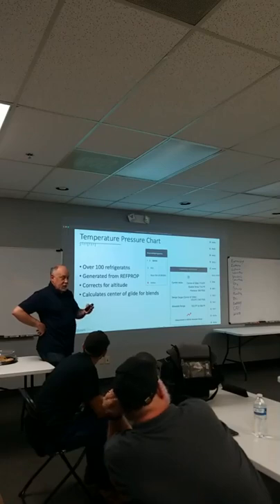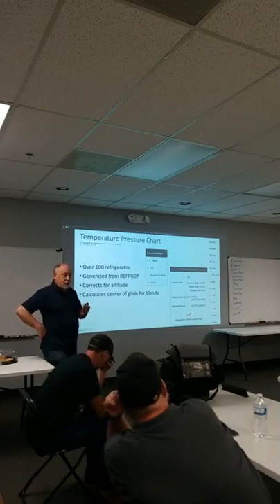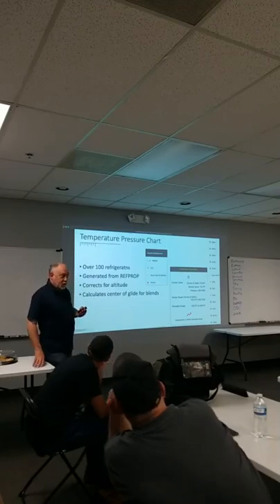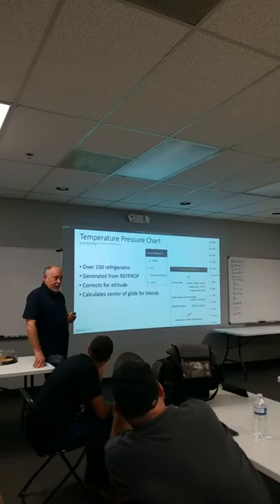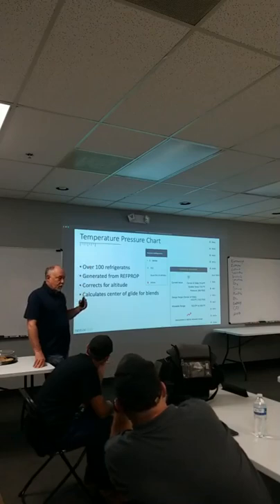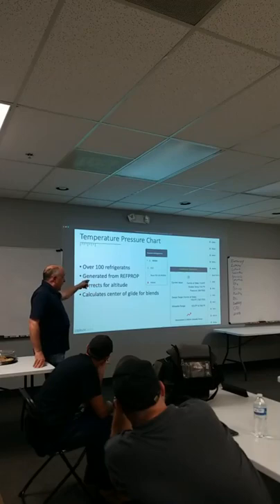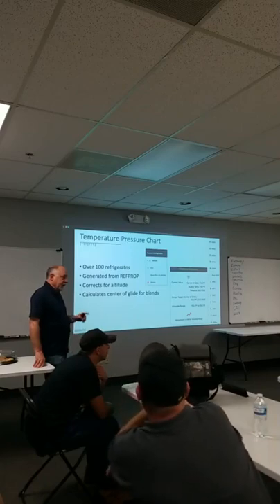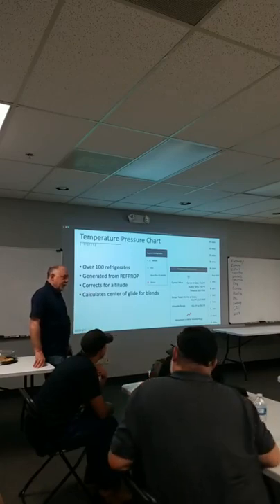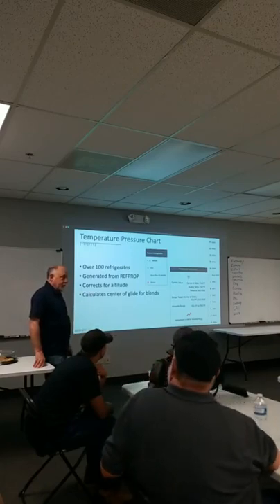So these gauges that we're using are all relative, so because we couldn't adjust the relative gauge, we would adjust the temperature pressure relationship of the refrigerant. They had a pressure temperature chart that was typically above 2,000 feet, and then they had another one for 7,000 feet, so you knew what the boiling relationship of the refrigerant was. But in a sealed system, it shouldn't matter. The sealed system doesn't care, but the gauge you're hooking up does. Your gauge is a relative gauge, right?